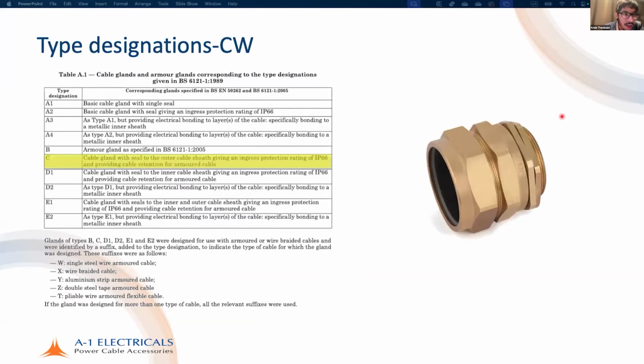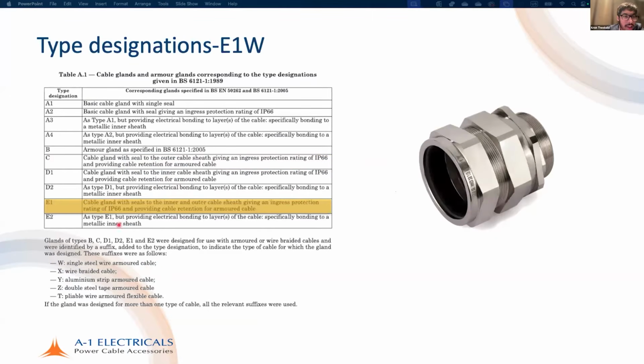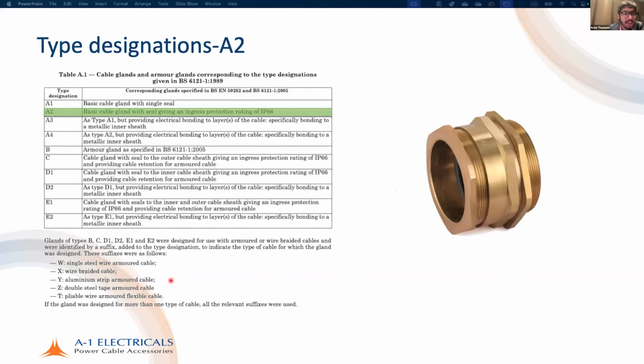A CW gland is a cable gland with a seal to the outer cable sheath providing an ingress protection of IP66, and it is designed to provide cable retention with the armored cable. The W means it is suitable for single steel wire armored cable. E1W means the cable gland provides a seal to the inner and outer sheath, giving an ingress protection of IP66 and cable retention. W means it is suitable for single steel wire armor. There are other letters for wire braided cable, aluminum strip armor, double steel tape armor, and so on. A2 means a basic gland which provides ingress protection, just for unarmored cables.